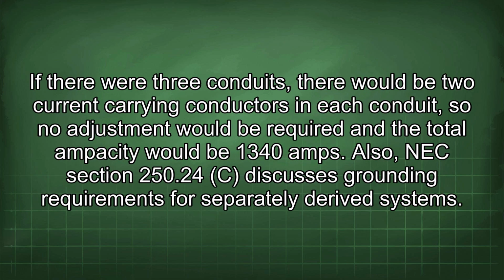If there were 3 conduits, there would be 2 current-carrying conductors in each conduit, so no adjustment would be required and the total ampacity would be 1340 amps. Also, NEC Section 250.24(C) discusses grounding requirements for separately derived systems.